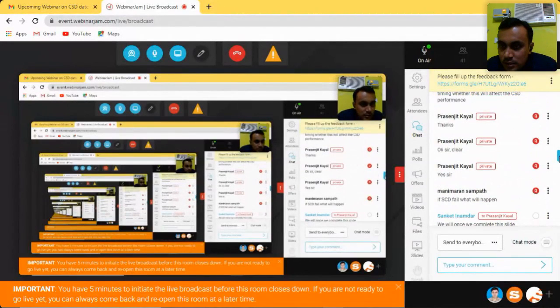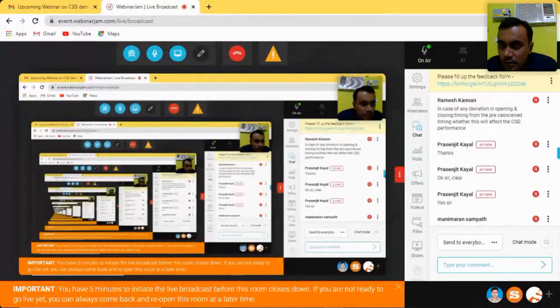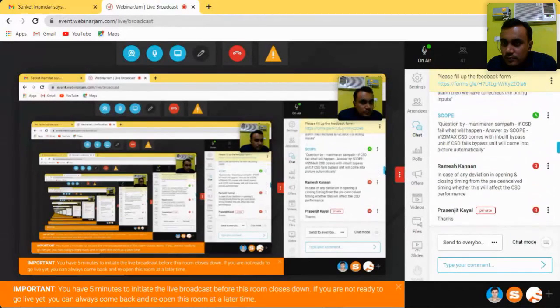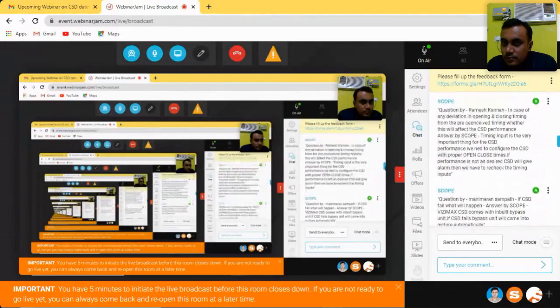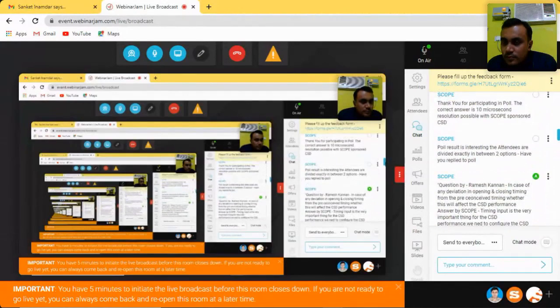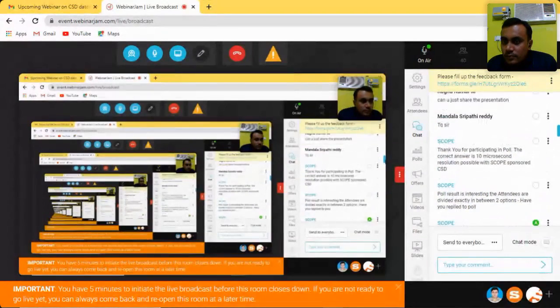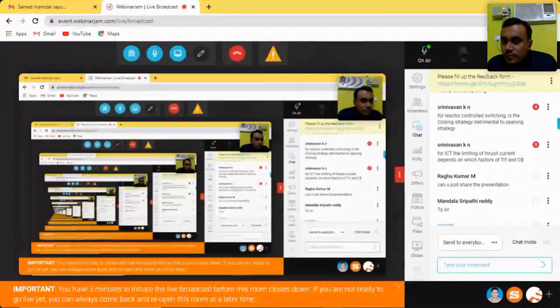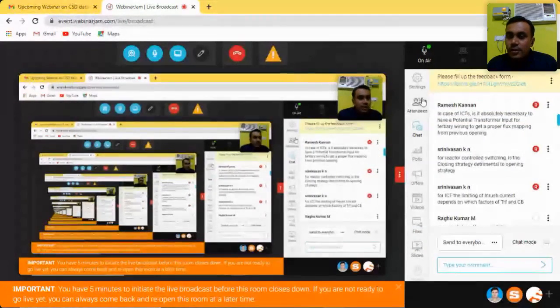There is an interesting question. For assessing breaker timing for close and open, what is your recommendation for CB testing kits? Is a CB analyzer kit used for assessing operating time accurately? So I think Mr. Srinivas wants to check whether we consider the time obtained with the CB analyzer kit, or the timing given by the CB manufacturer whenever it has been given to the substation. So, have you got this point?